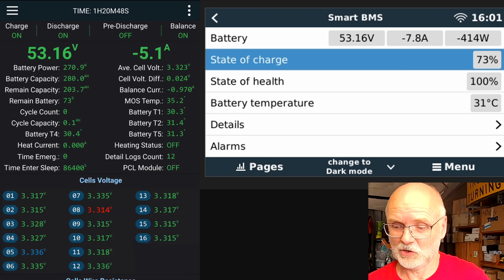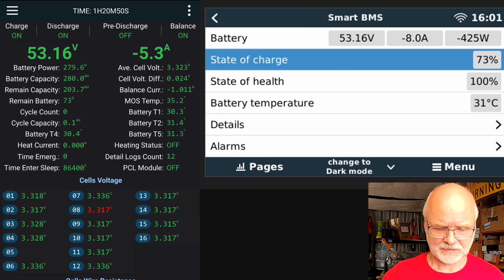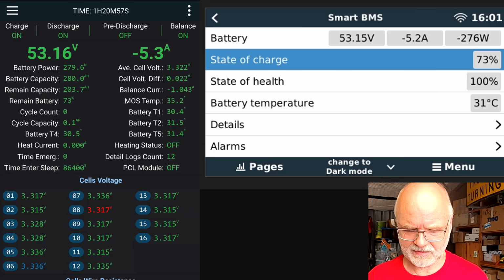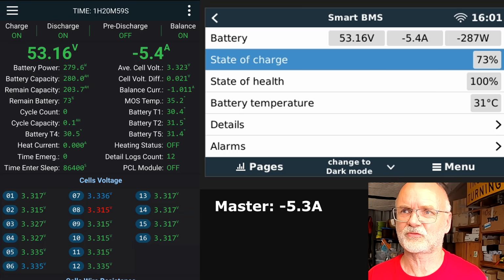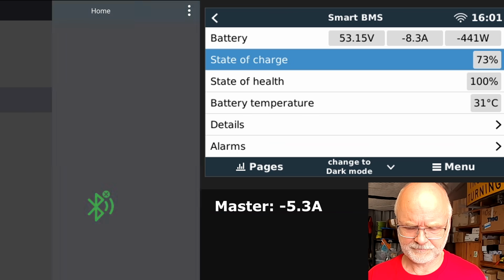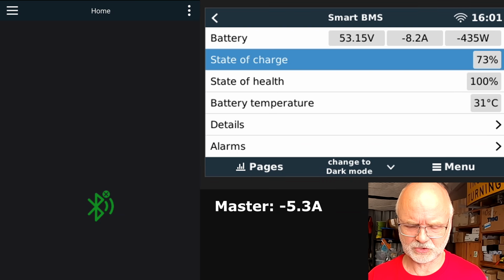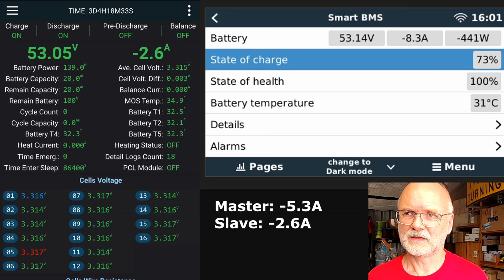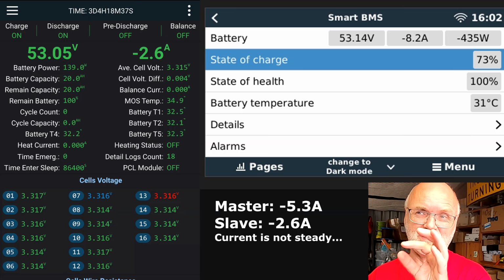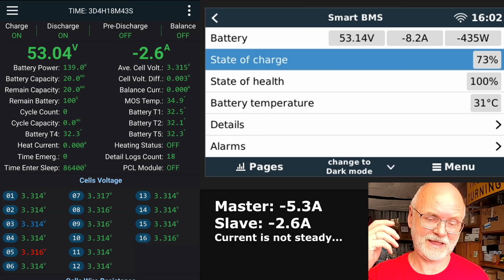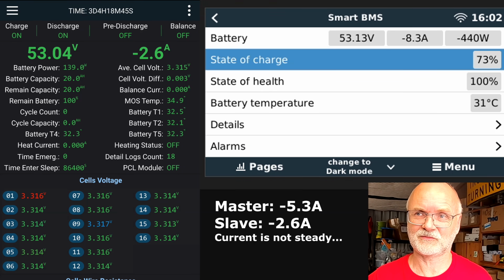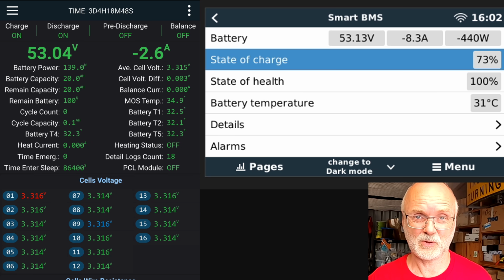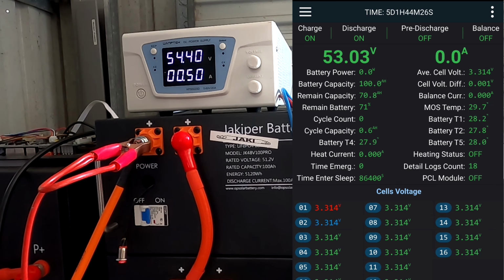So I have now connected a load to our 2 batteries, and this is showing our master BMS with negative 5.3 amps. Let's see what the slave battery shows. Negative 2.6, which makes then negative 8.3 in your inverter. So it is actually adding these 2 currents together and showing this correctly in the Victron system or your inverter. Perfect. So in the next step, we want to test the resolution or sensitivity of the JK-BMS.